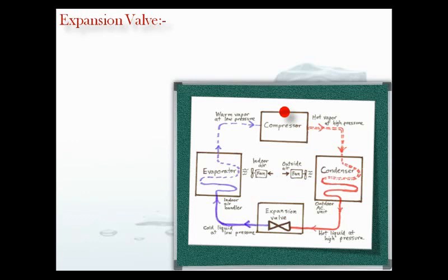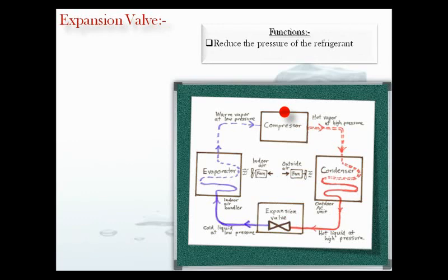The thermostatic expansion valve performs the following functions. First, it reduces the pressure of the refrigerant. The first and foremost function is to reduce the pressure of the refrigerant from the condenser pressure to the evaporator pressure. The thermostatic expansion valve has a constriction or orifice through which the pressure of the refrigerant drops suddenly to the level of evaporator pressure. Due to this, the temperature of the refrigerant also drops down suddenly, producing a cooling effect inside the evaporator.